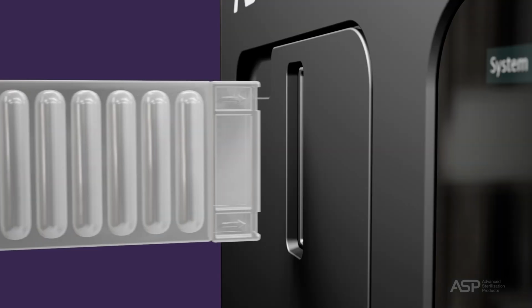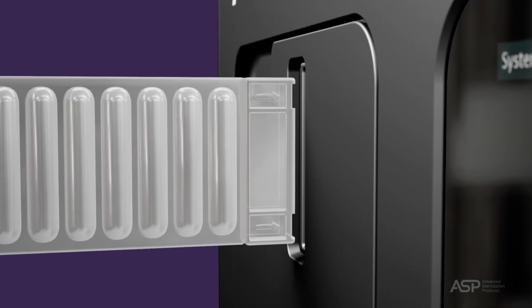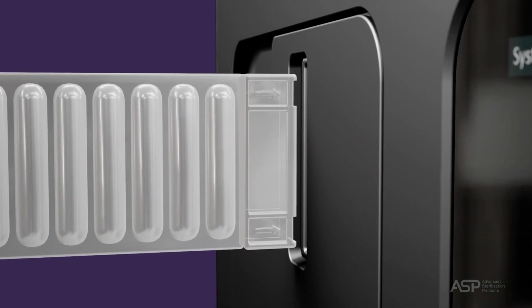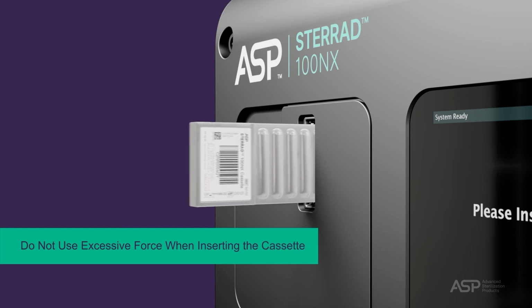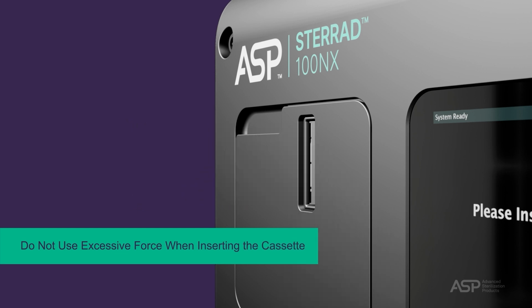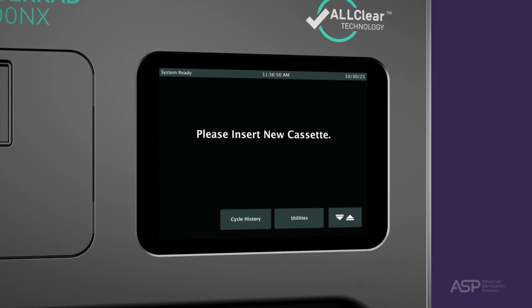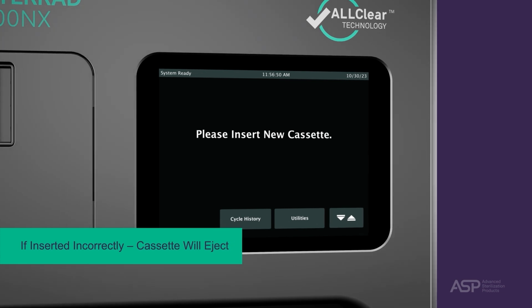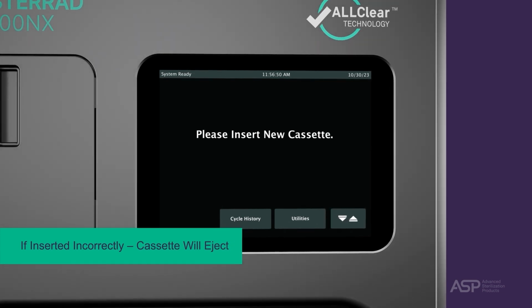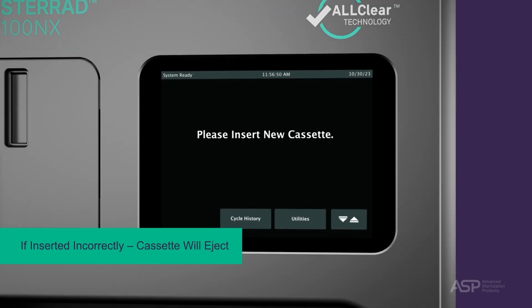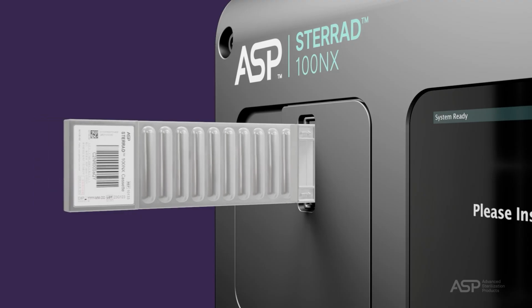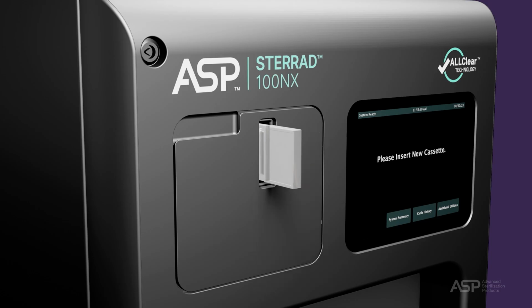Position the cassette so that the arrows are pointing straight into the cassette door slot of the sterilizer. Do not insert the cassette at an angle and do not use excessive force. If the cassette is inserted incorrectly, the sterilizer will eject the cassette, and the screen will ask the operator to remove and reinsert the cassette. Insert the cassette into the cassette slot until the system detects and pulls the cassette in.